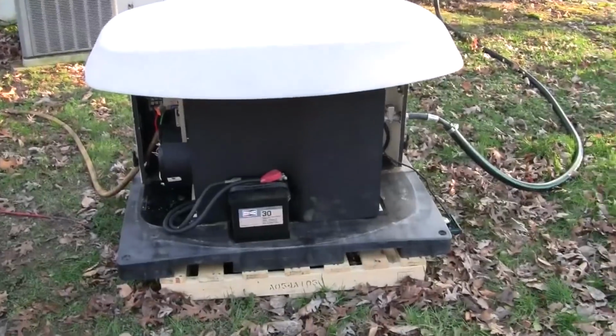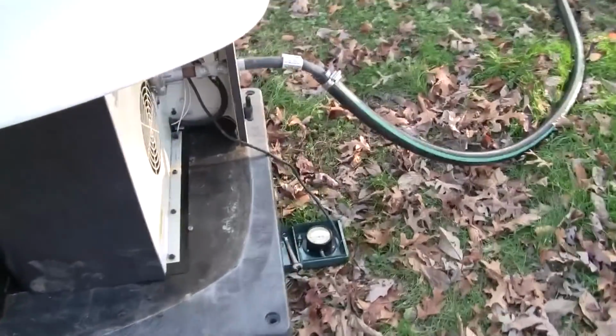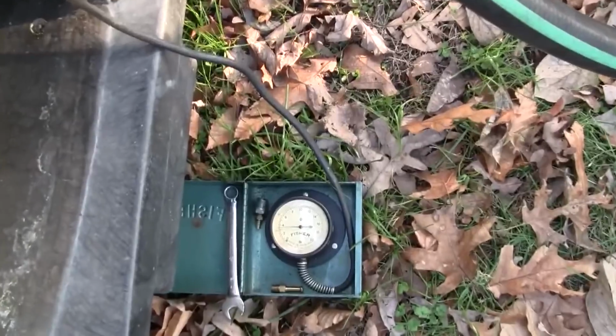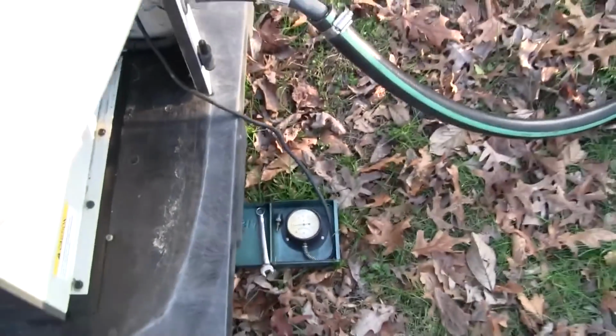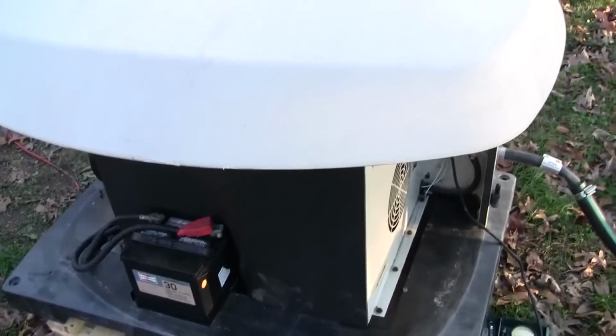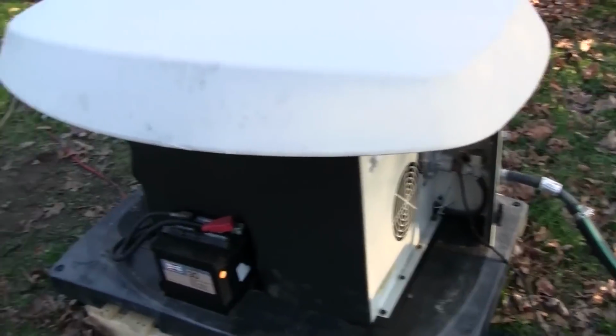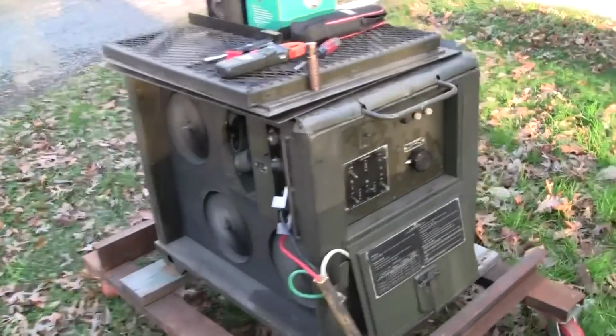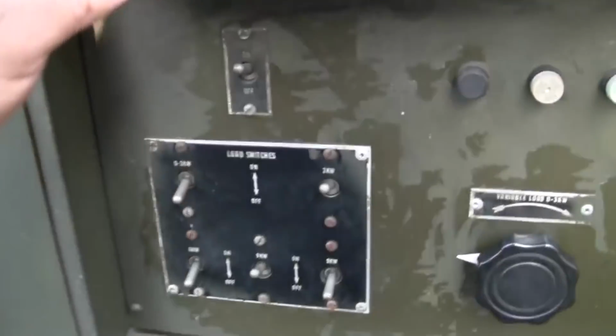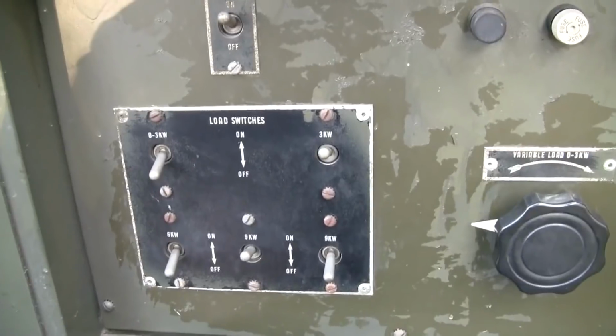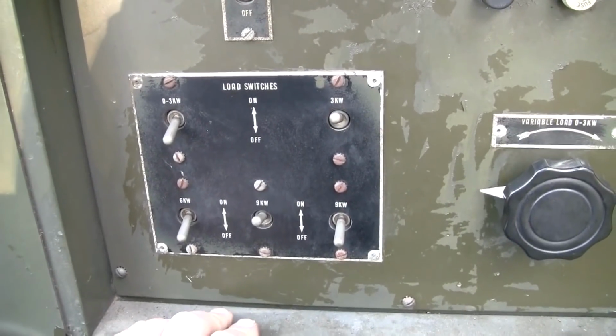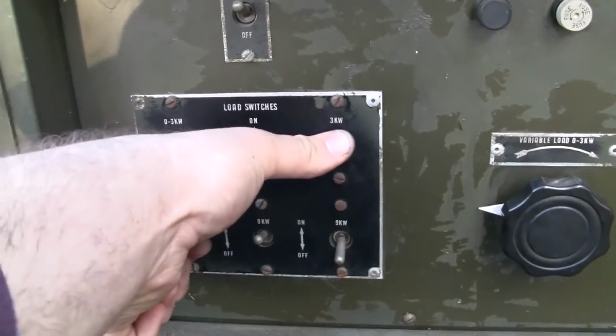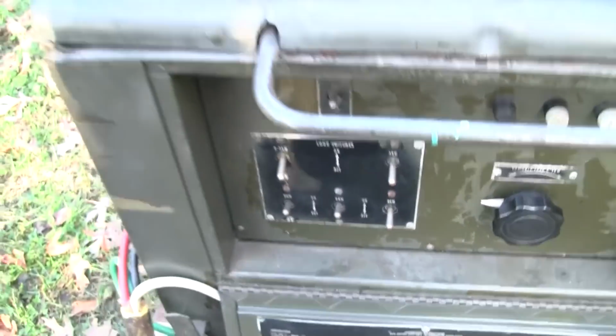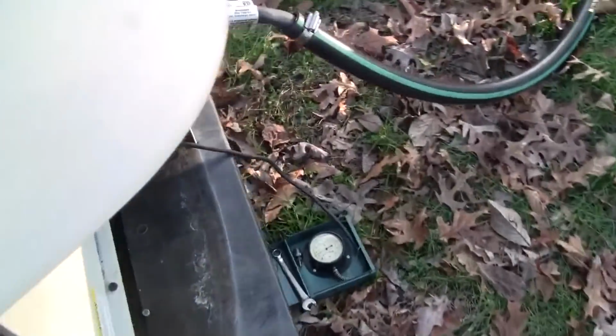I think it's time to give it all she's got. Remember, we are at about 4.5 to 5 inches of water column, so we're at the ragged edge of the gas pressure range. We are at 12 kilowatt. Let's give her 15. Pressure's holding.